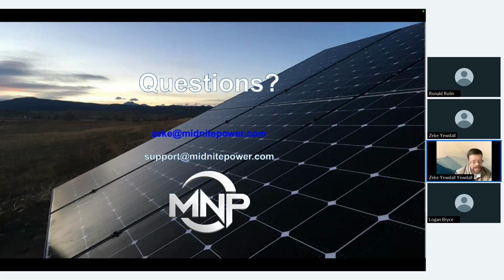We got a question on maximum PV array size. So we specify 15 kilowatts of PV array. It's actually a little more complicated than that. You want to definitely stay below those amperage limits because exceeding the amperage can damage the machine. So exceeding that maximum 40, 30, 30 for the Imax or 30, 22, 22 for the operating amperage, that can damage the machine. But if you look, say you had a really high voltage array, 30 amps, you can get a lot of watts out of that. So if you were running higher voltage arrays, you can actually put a lot of power, but you're just not going to get that much power into the machine.